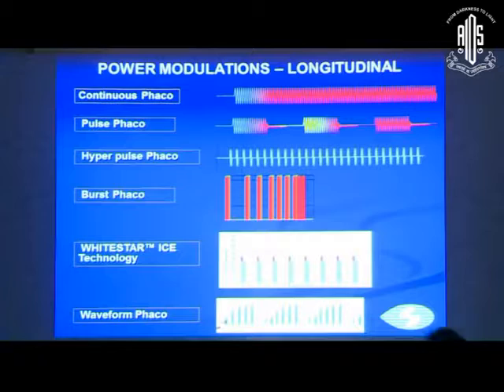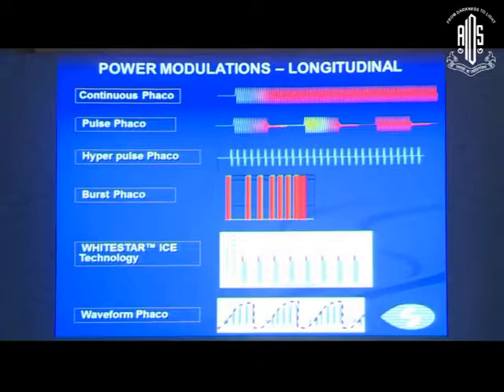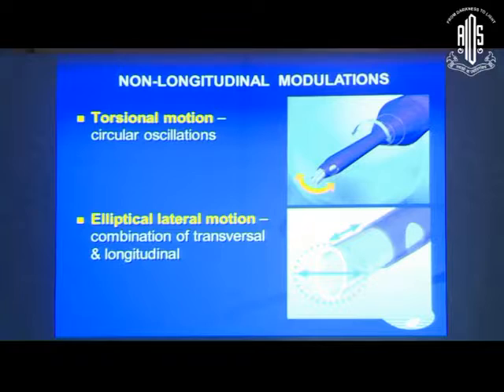First, about power modulation. We have all been through continuous and pulse modes, which have already been discussed. The new power modulations are the two non-longitudinal types: torsional, which is a circular oscillation, and elliptical, which is a combination of transversal and longitudinal.